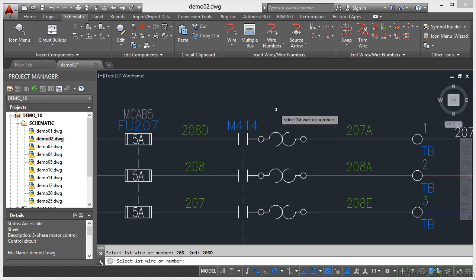But the lovely thing about this is the AutoCAD Electrical Project Database is updating in the background as well. You don't just move wire numbers. Don't use the move command and move the wire numbers. You use the swap tool. If you move those wire numbers, the wire numbers remain the same in the database but are different on the drawing, and that can cause absolute chaos when you start reporting later on down the line from your AutoCAD Electrical Project.